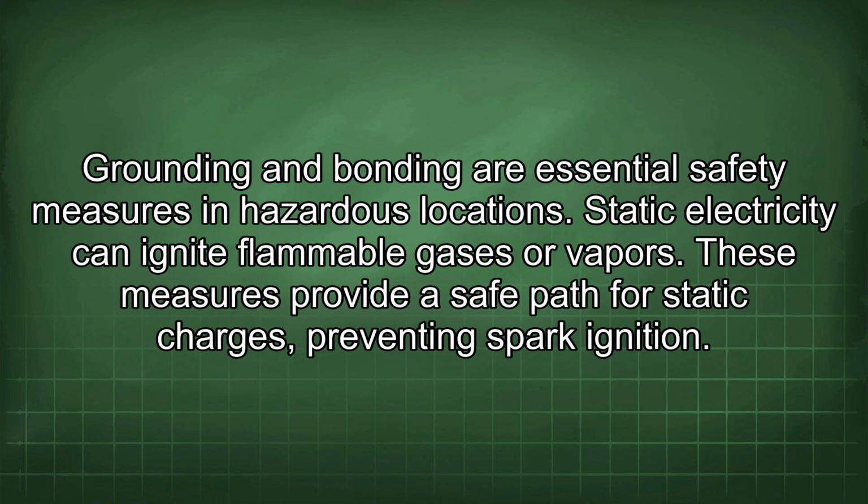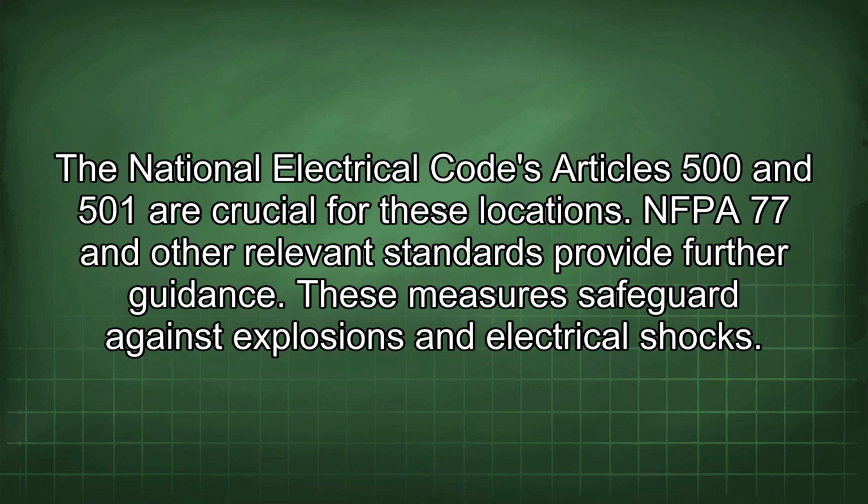Grounding and bonding are essential safety measures in hazardous locations. Static electricity can ignite flammable gases or vapors. These measures provide a safe path for static charges, preventing spark ignition. The National Electrical Code's Articles 500 and 501 are crucial for these locations. NFPA 77 and other relevant standards provide further guidance.